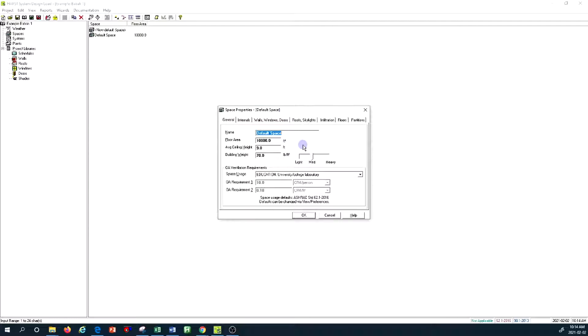The typical floor height is another input. If you have a space with a plenum — where you have a suspended ceiling, drywall, or hard ceiling — you put the total height from floor to ceiling level. I have this set to nine feet as an average ceiling elevation. Building weight is information I tend to keep at medium for now.